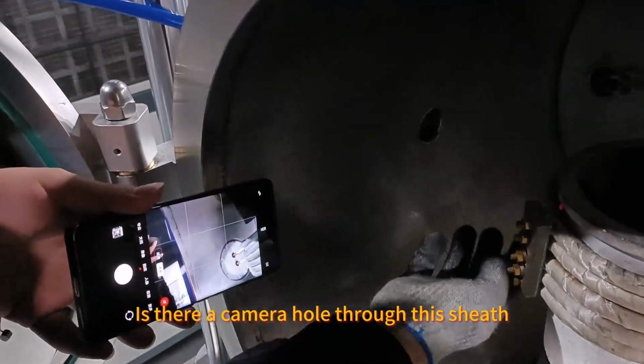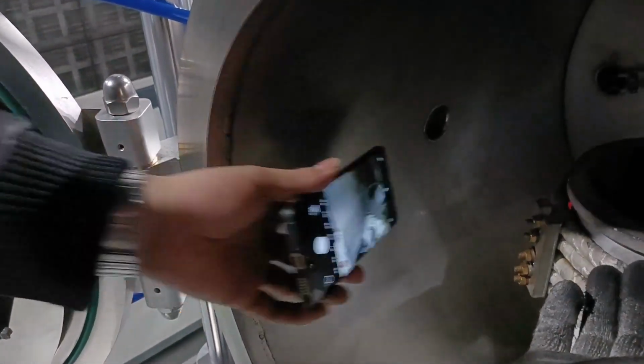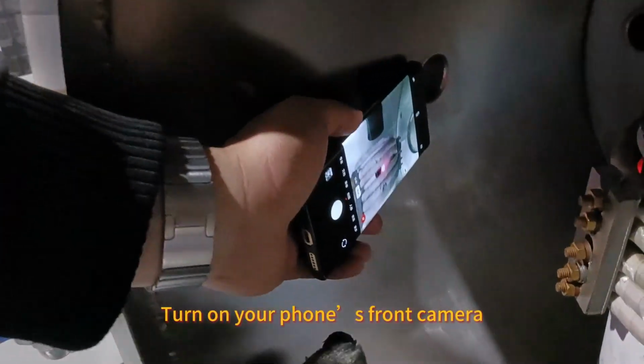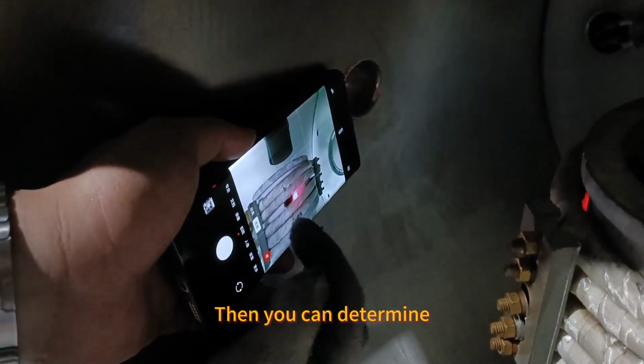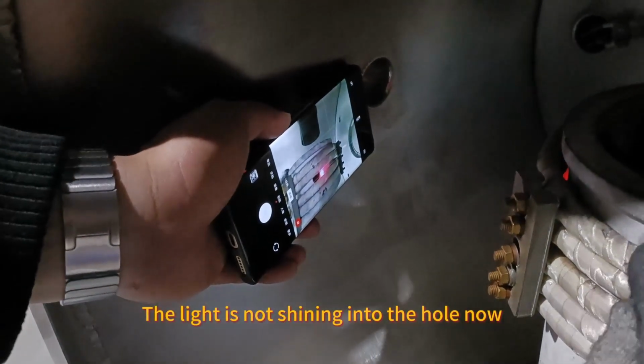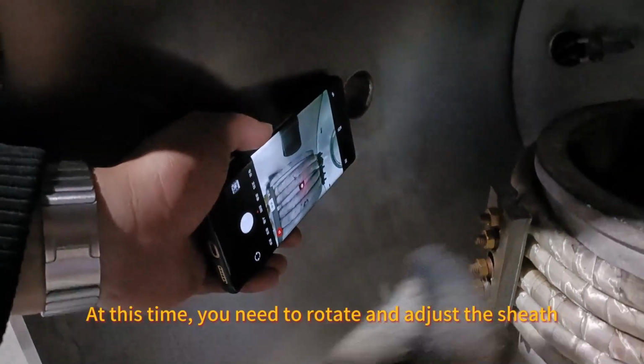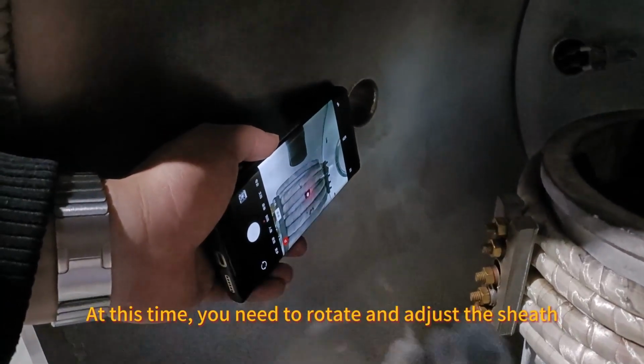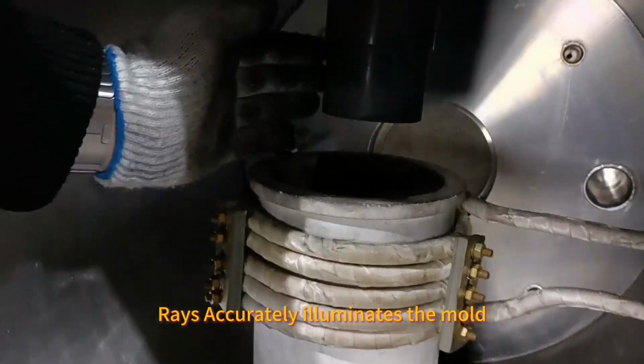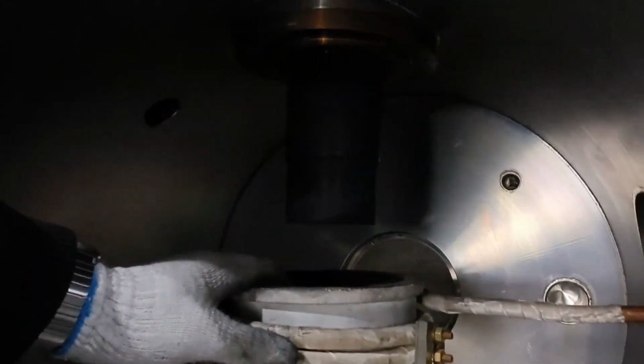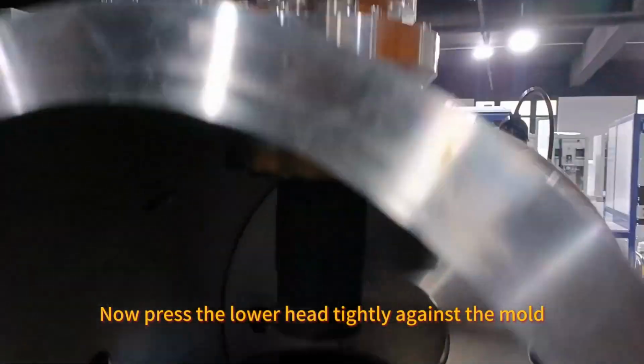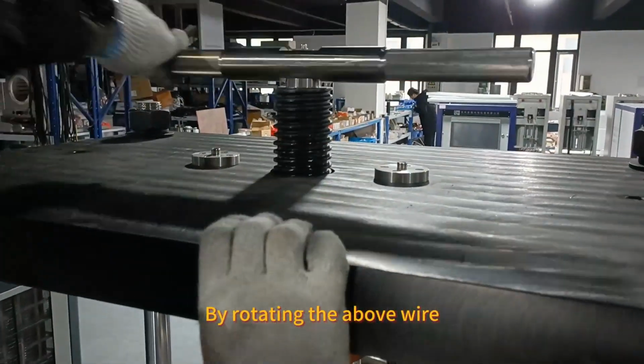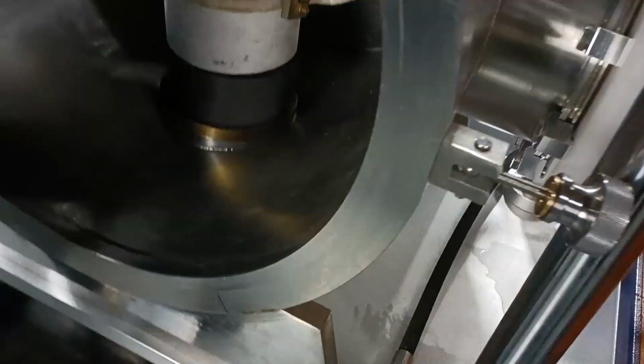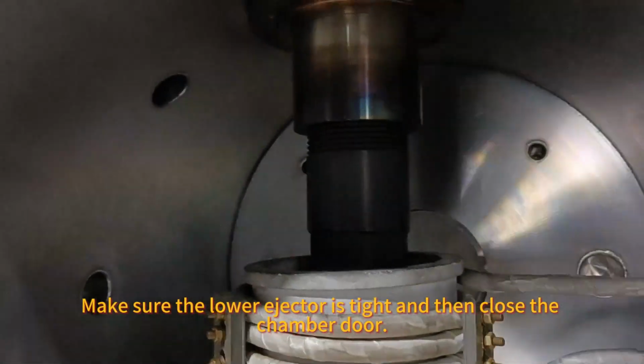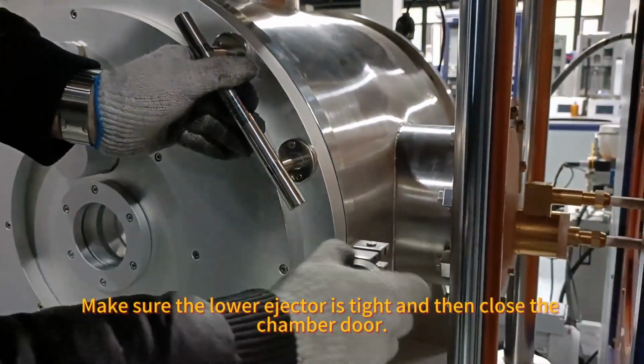Is there a hole for the infrared rays to pass through this sheath and irradiate the mold? Turn on your phone's front camera and put it here, without blocking the infrared hole. Then you can determine that the light is not shining into the hole now. At this time, you need to rotate and adjust the sheath. Okay, now the rays accurately illuminate the mold. Now press the lower head tightly against the mold by rotating the screw above. Make sure the lower ejector is tight and then close the chamber door.